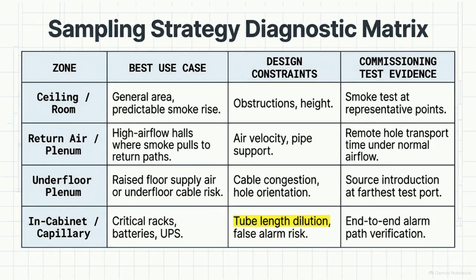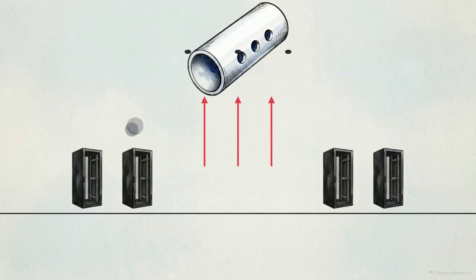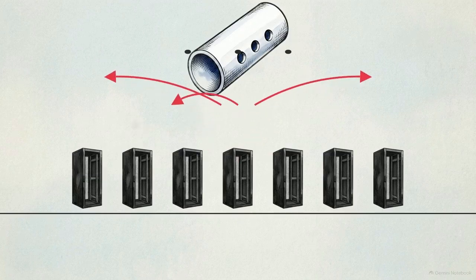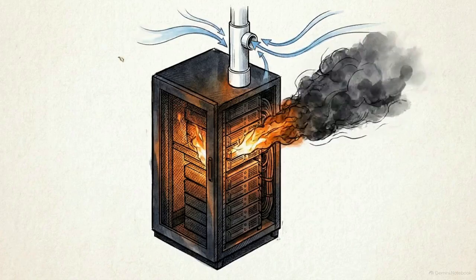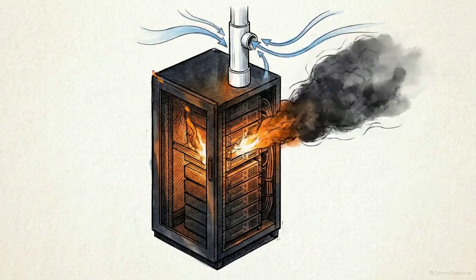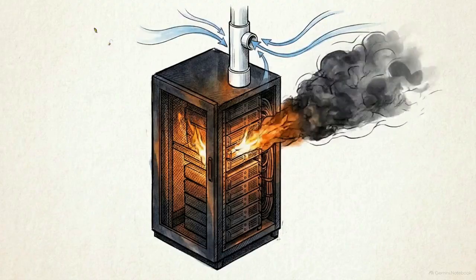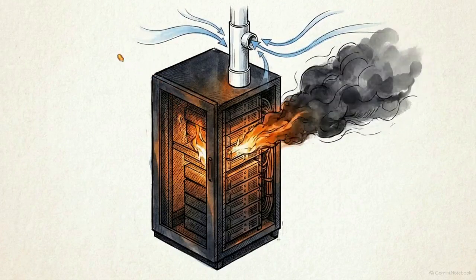prevent excessive sample dilution. Any subsequent change in CRAC airflow, aisle containment, or rack density will alter smoke movement, which can invalidate the existing sampling architecture. The physical placement of sampling points must match the room's aerodynamics, or the system will continue to detect clean air while a fire burns nearby.